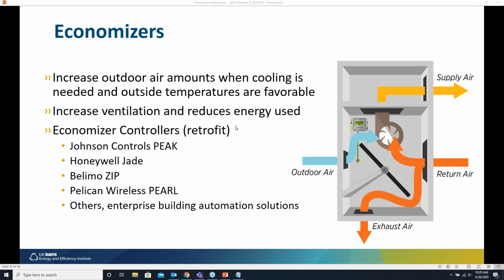I want to talk a little bit about economizers. So economizers are a device. This is a cross-sectional sketch of an HVAC system, and this is the damper here, this black line that opens and closes to bring outdoor air into the building. What an economizer does is that when conditions are favorable outside, say we're trying to cool the building, but outside it's 50 degrees, it can open up the damper and bring in extra outdoor air when it's favorable to do so. This is a really great way to get extra outdoor air into your space and save energy.